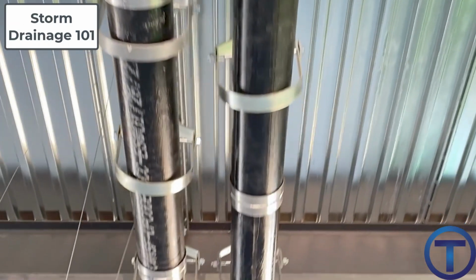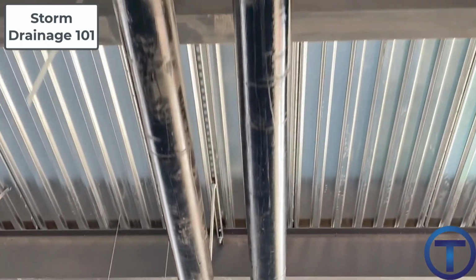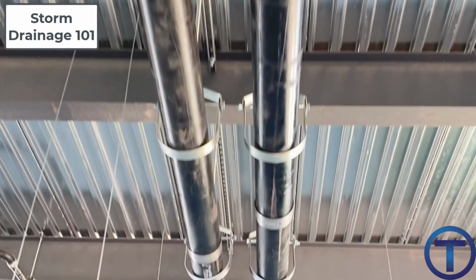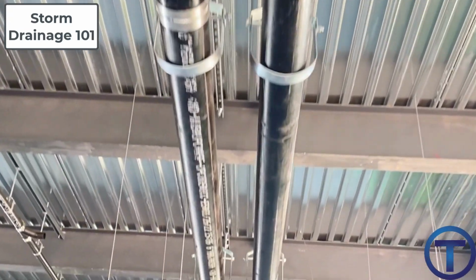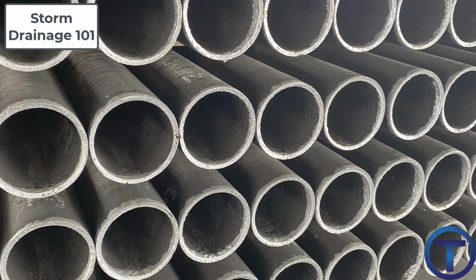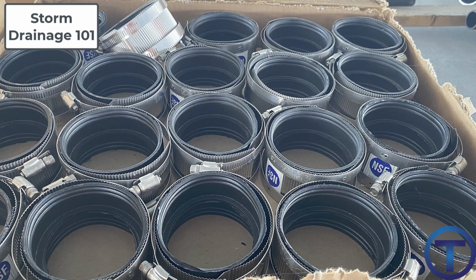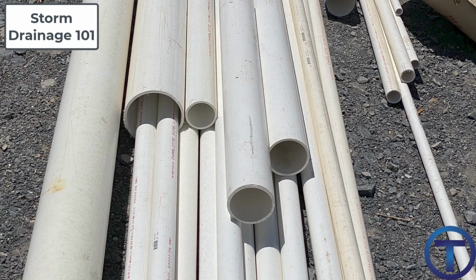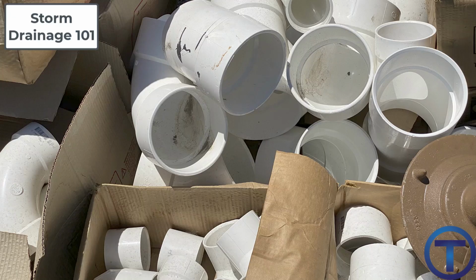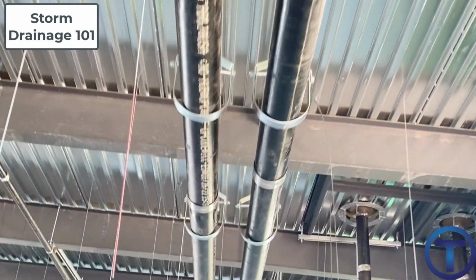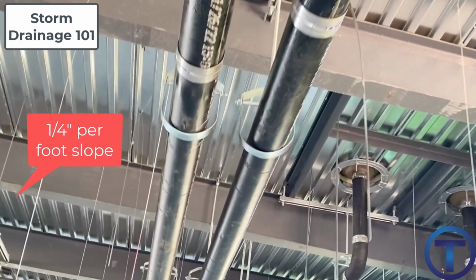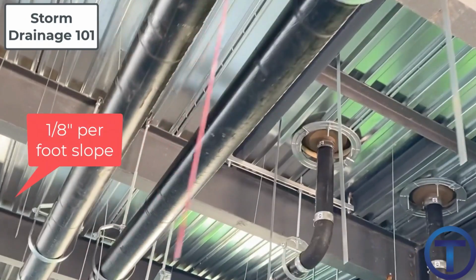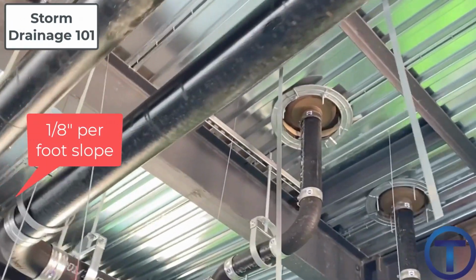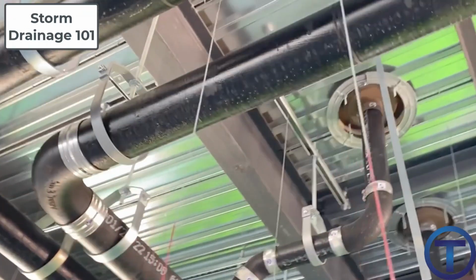Now, they are similar to other drains. We're talking drainage, waste, and vent, in that we use the same materials. You can use cast iron with no hub, or you can also use PVC or other approved drainage pipe and fittings. And they also run with similar slopes. 1/4 inch per foot is ideal. With larger pipes, you can go 1/8 inch per foot. These slopes are designed to convey that water out through the pipes.